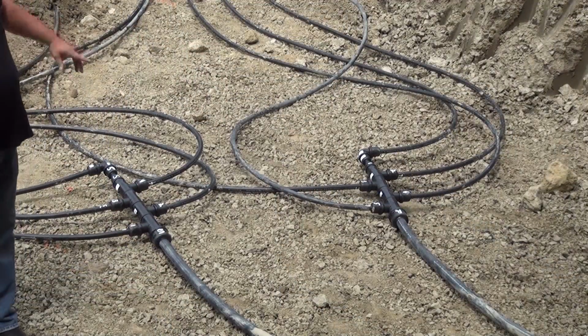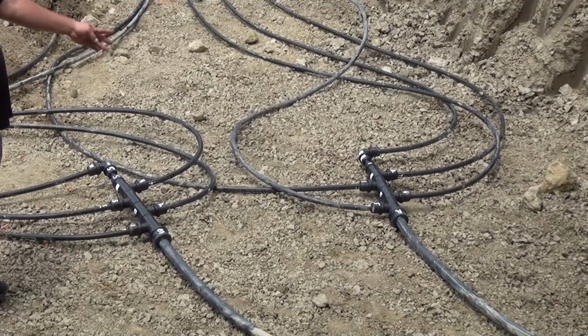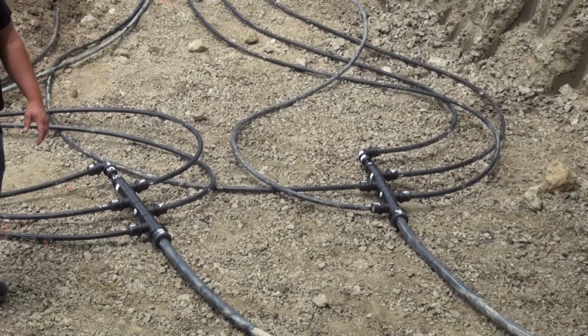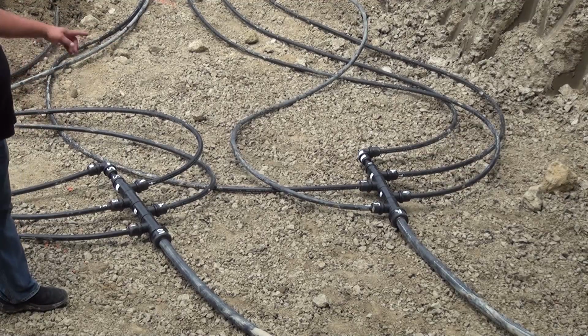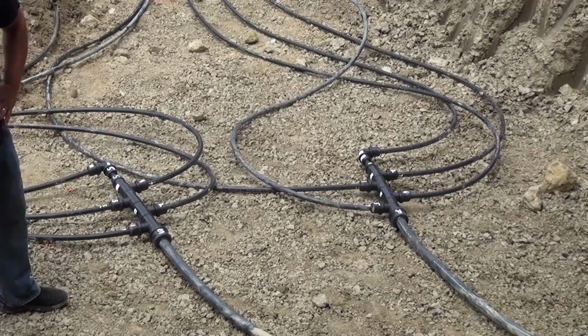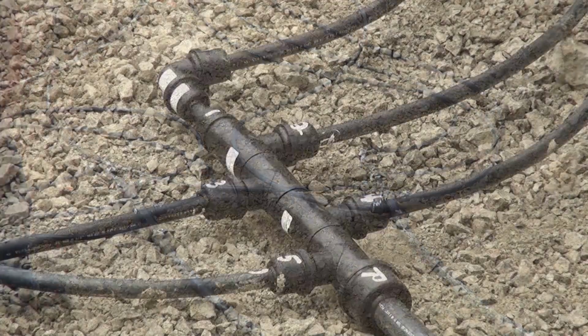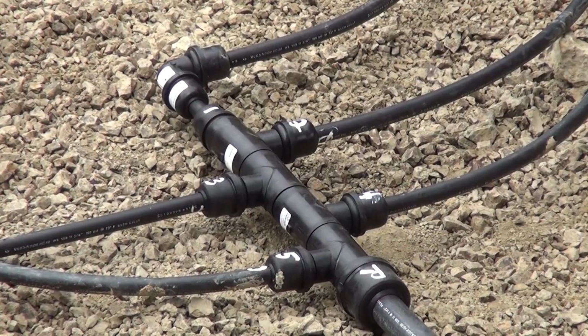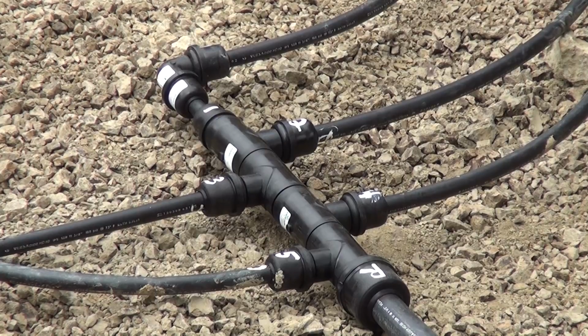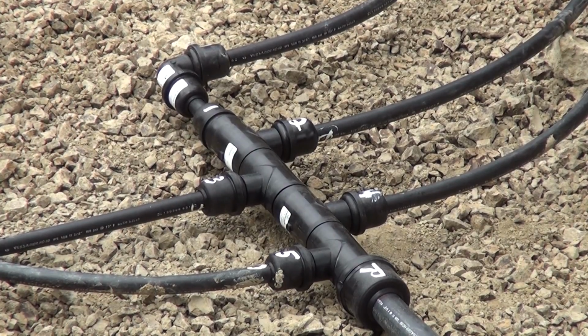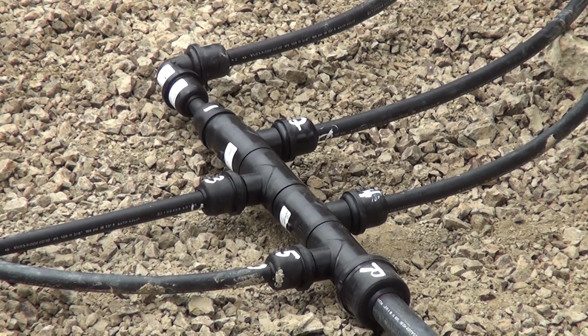Now the pipes that are coming from the loop field here that go into the two-pipe reverse return manifold system are tied in with geostab adapters. Very tight fit. Once they're pressed inside, you're going to need a Chevrolet pickup truck to pull them apart. After they're underneath the ground, they're well buried, sealed, and good forever.